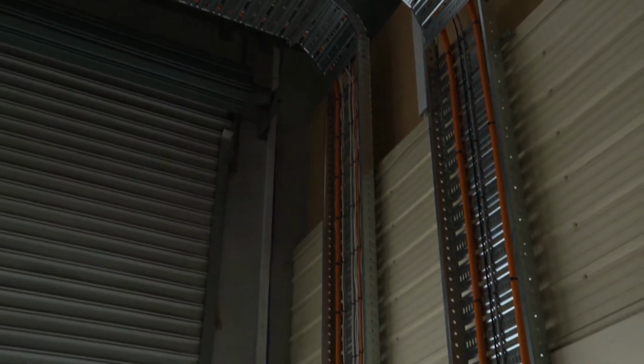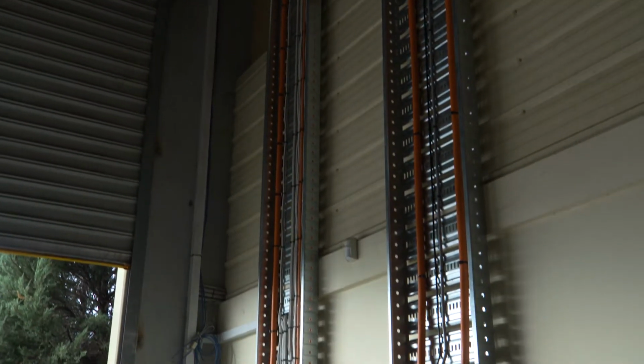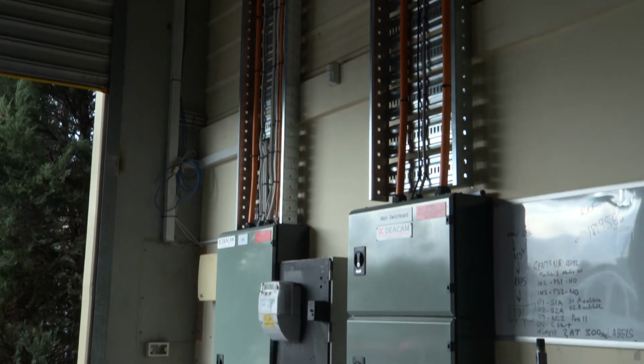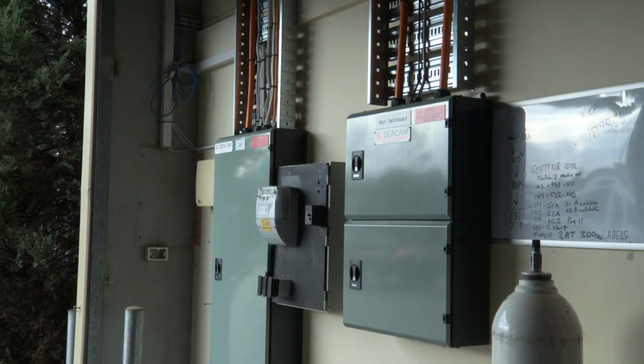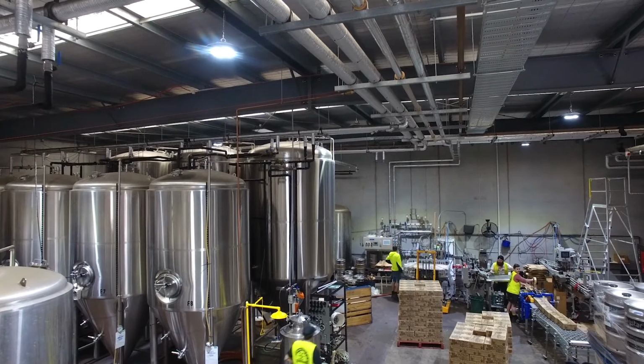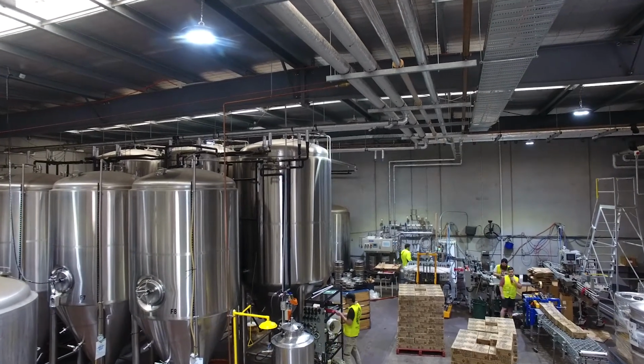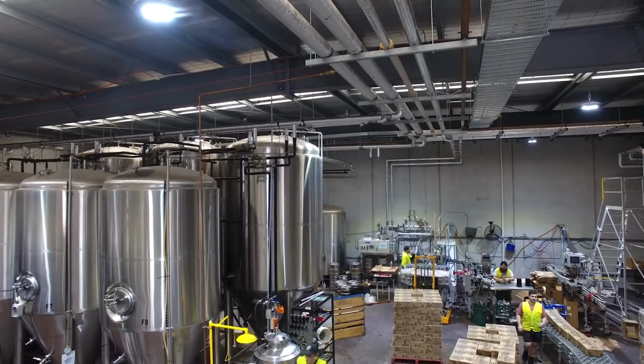And so we have power coming in, not enough, but we also were feeding it incorrectly down the wire as well. Our glycol system, which controls all the tanks, they have 2 compressors and they have 2 pumps. They only need 1 through winter, but when it needs more, the second pump comes on, the second compressor comes on. So rather than being at like at 46, 50 amps, it got to about 83 amps. Well, that's our load to our site.